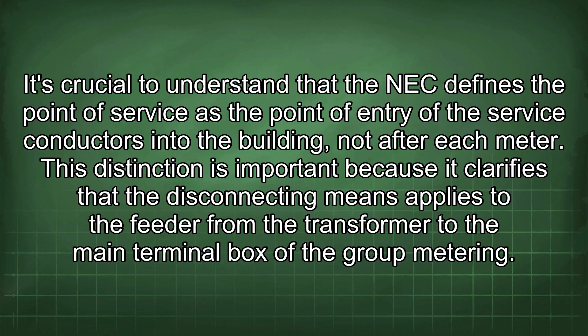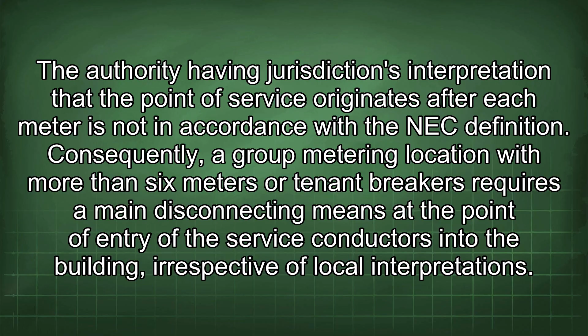The authority having jurisdiction's interpretation that the point of service originates after each meter is not in accordance with the NEC definition. Consequently, a group metering location with more than 6 meters or tenant breakers requires a main disconnecting means at the point of entry of the service conductors into the building, irrespective of local interpretations. While some areas may have a common practice of allowing group metering without a main disconnect, this does not align with the NEC. It is essential to prioritize code compliance to ensure the safety and reliability of the electrical system.